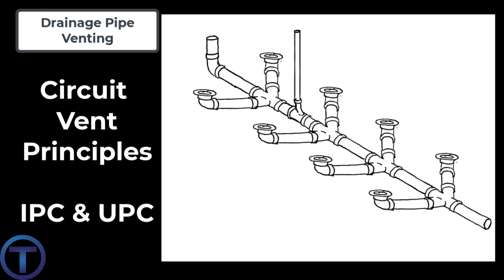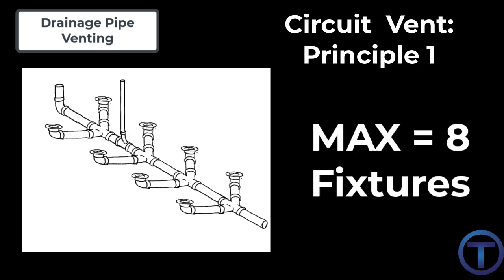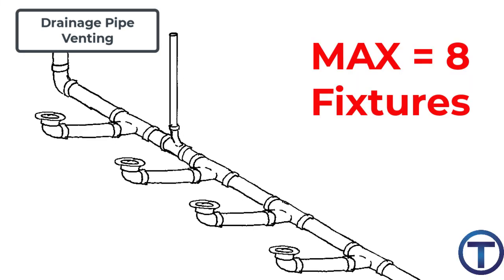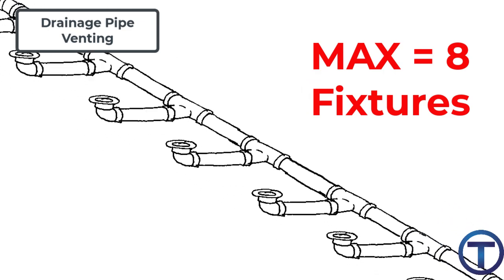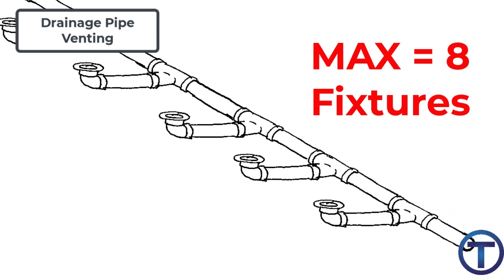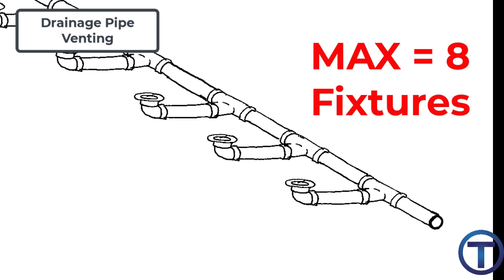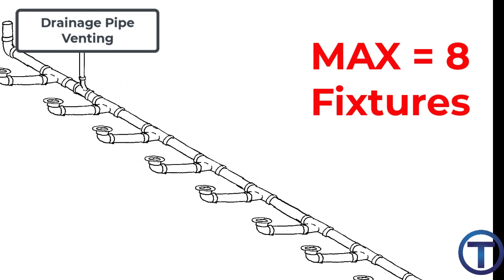Let's have a look at the basic principles governing the installation of circuit vents. These principles come from both the International Plumbing Code and the Uniform Plumbing Code. Circuit vent principle one: no more than eight fixtures connecting to a horizontal branch are permitted to be circuit vented. That really provides a lot of latitude — you can have up to eight fixtures connected to this horizontal branch, being served by a single circuit vent.